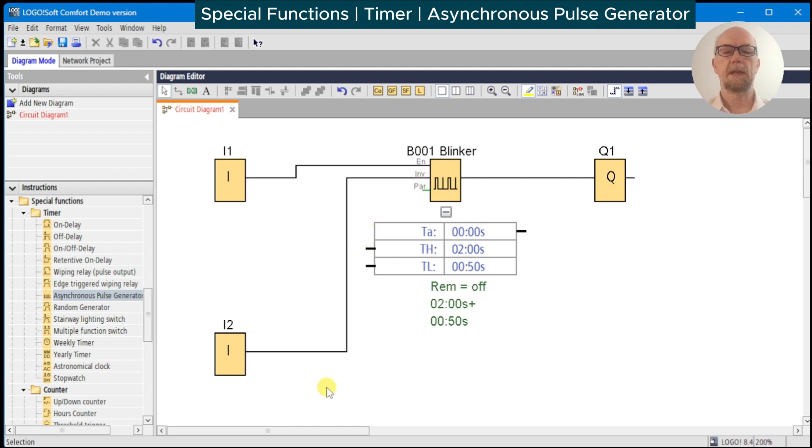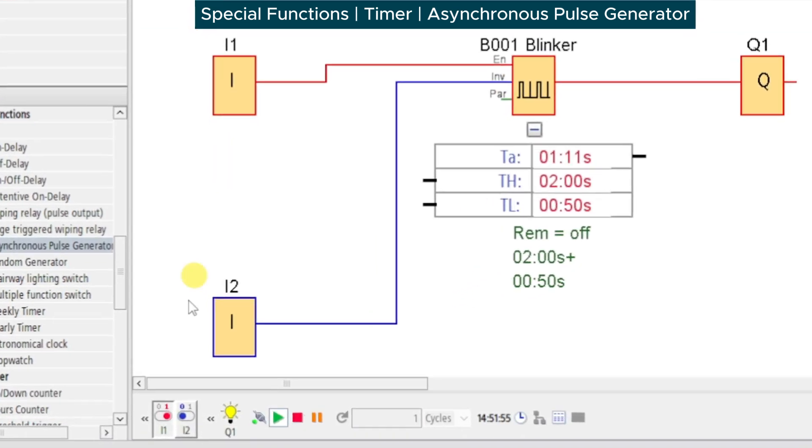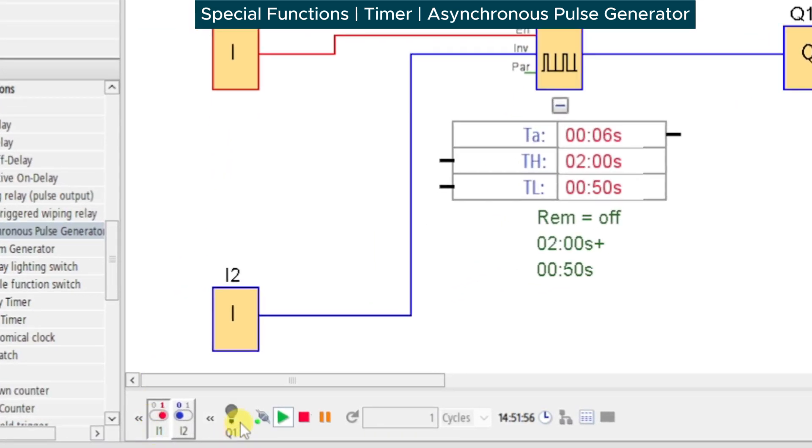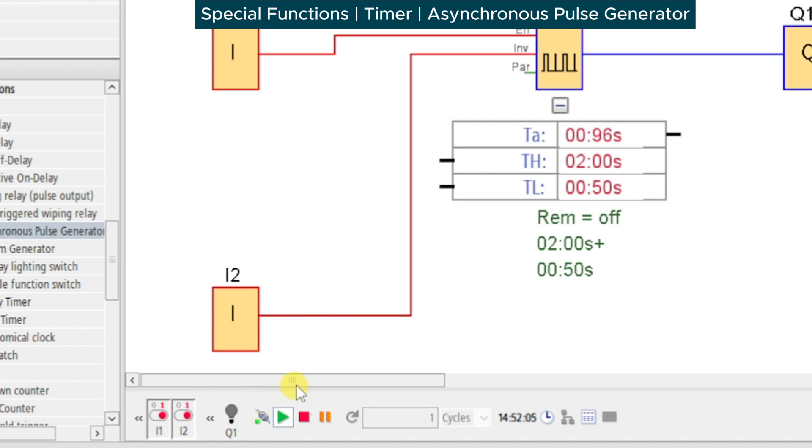We can use the inverse input to swap the time high and time low. So run the timer normally, observe the lamp two seconds on, half a second off. By turning the inverse input high, we get half second on and two seconds off.